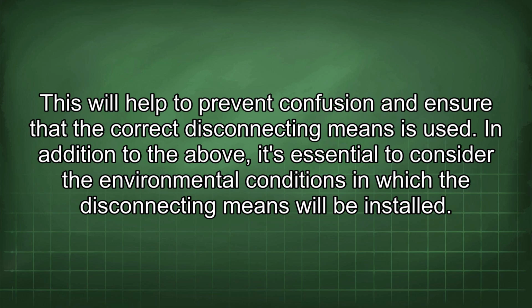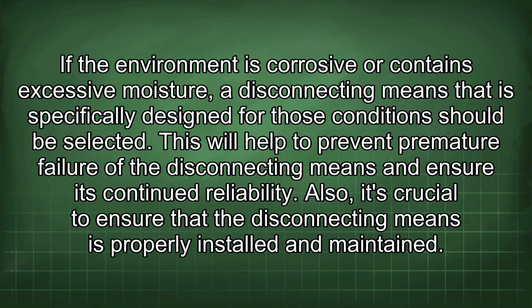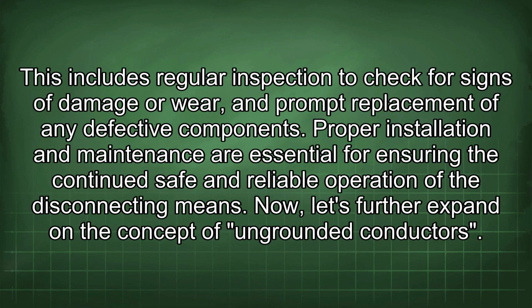In addition to the above, it's essential to consider the environmental conditions in which the disconnecting means will be installed. If the environment is corrosive or contains excessive moisture, a disconnecting means that is specifically designed for those conditions should be selected. This will help to prevent premature failure of the disconnecting means and ensure its continued reliability. Also, it's crucial to ensure that the disconnecting means is properly installed and maintained. This includes regular inspection to check for signs of damage or wear, and prompt replacement of any defective components. Proper installation and maintenance are essential for ensuring the continued safe and reliable operation of the disconnecting means.